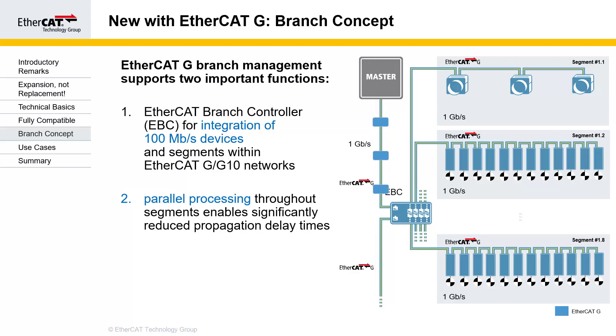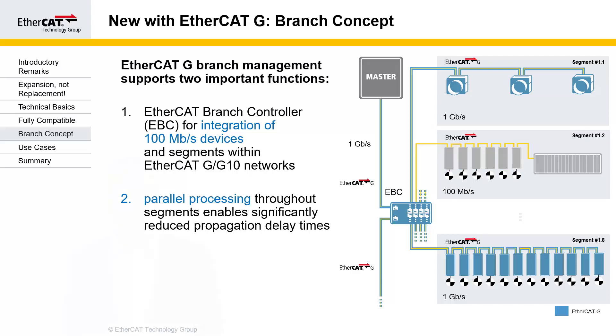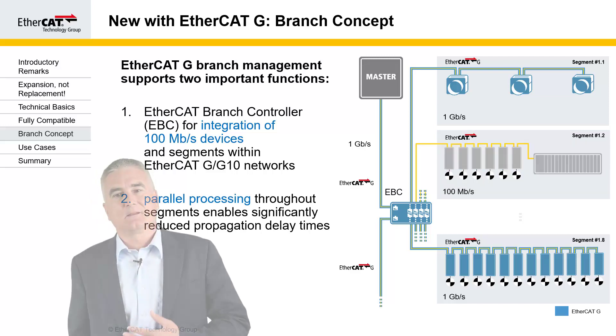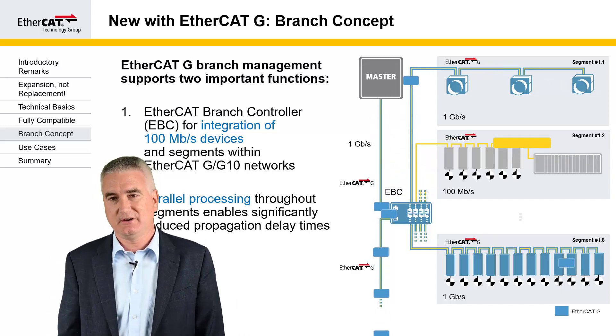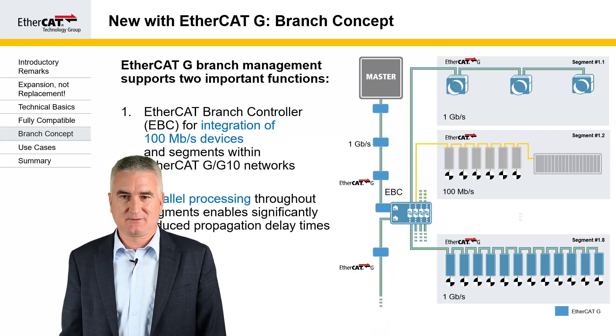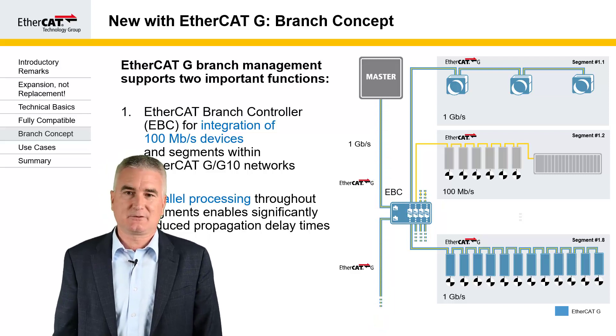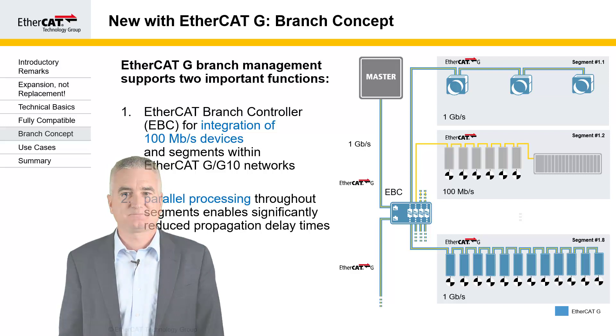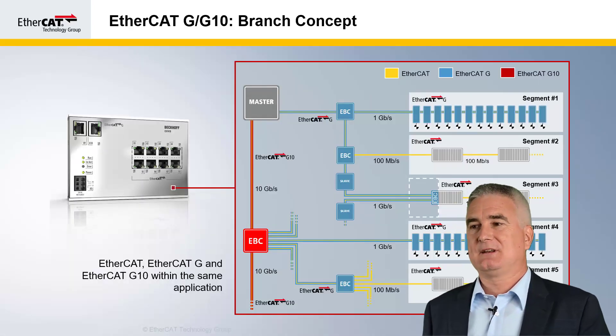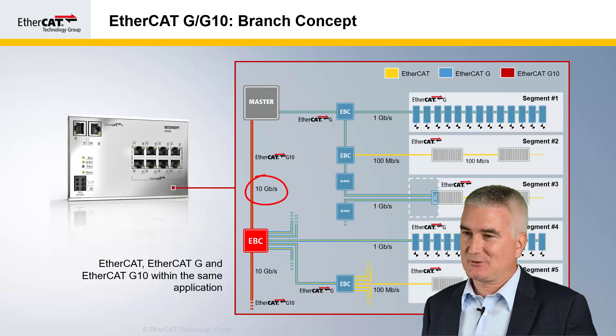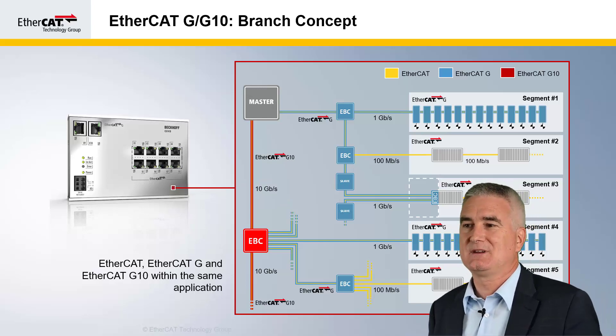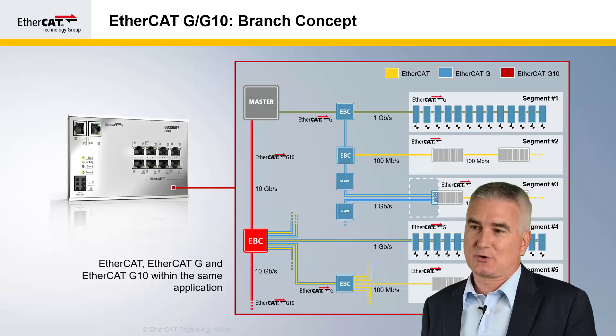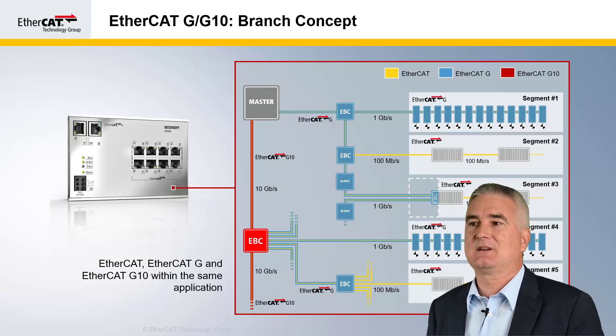In the same way, we are running multiple segments in parallel and saving on the propagation delay side of the communication time. We can even combine 100 megabit and gigabit segments underneath a branch controller. In the 100 megabit segment, the frame is a 100 megabit frame and then switches back to gigabit on the way back to the master. This works not only with gigabit and 100 megabit, but also with 10 gigabit. So we can have underlying networks from 10 gigabit to gigabit to 100 megabit and can mix and match according to the devices and application requirements.